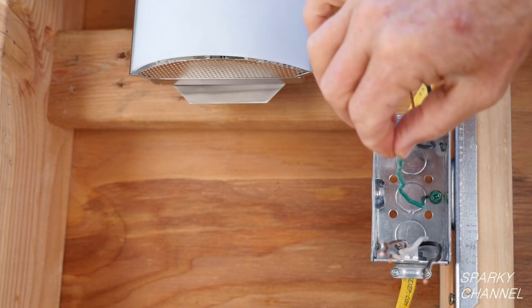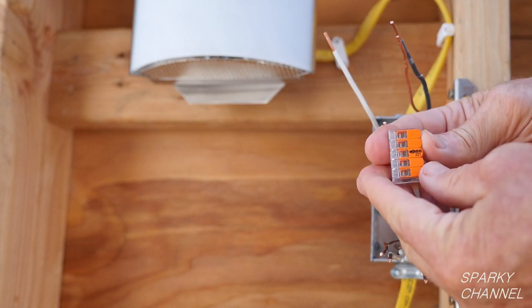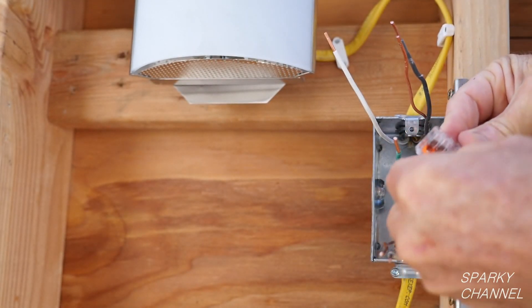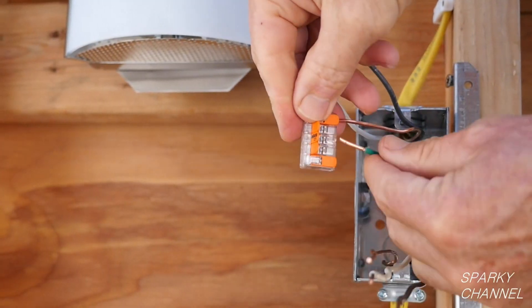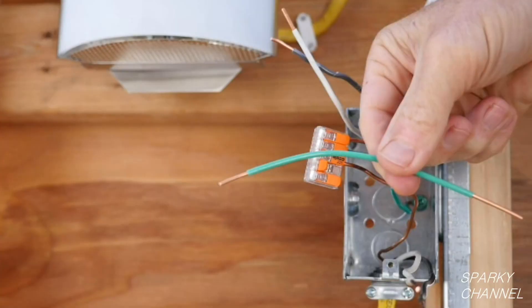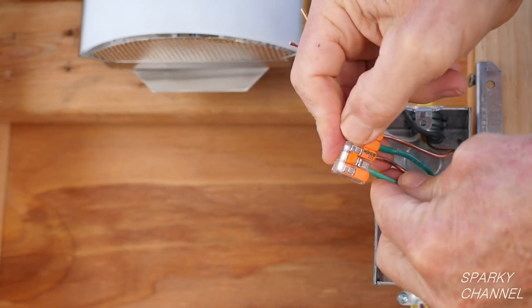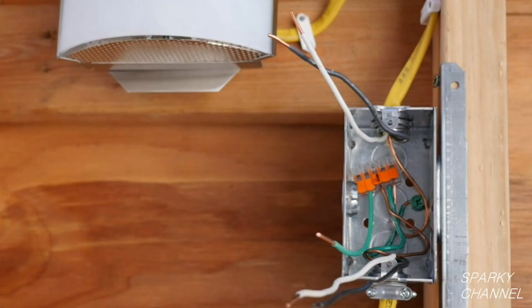First, I will hook up the ground wires. There are three ground wires in the box and I will need one grounding pigtail to go to the switch. This is a Wago 5 connector lever nut. Open four of the levers. Put a ground wire all the way in the connector and close the clamping lever. Repeat for each ground wire, pushing each wire all the way in and clamping it shut. Now I will put my pigtail in the connector and close the lever. This leaves one open space in the 5 connector lever nut. Push the grounds back into the back of the box.